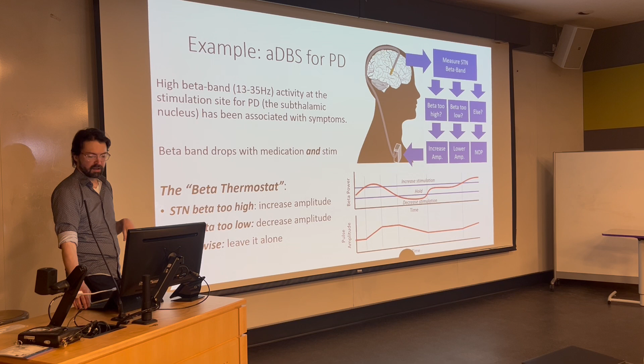The trick though is to do this closed loop, you suddenly now have a device which has to do sensing, processing, classification, and have a dynamic state table that defines all the actions it takes in every single different neural sensing scenario. Before, a neurologist was there just trying out, for this contact, let's do amplitude, pulse width, and frequency changes, and let's try a different one. How the heck is that neurologist going to configure this table? I'll tell you, they can't. They need a PhD to do it, right?